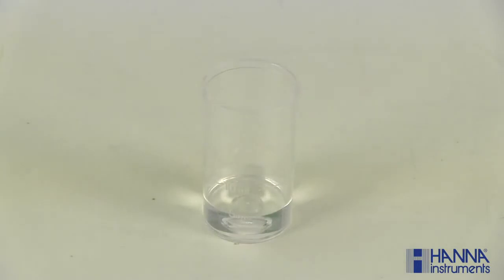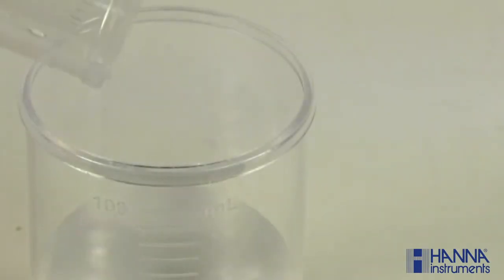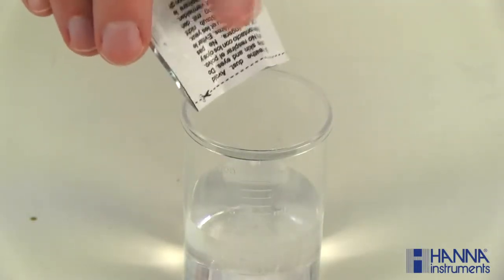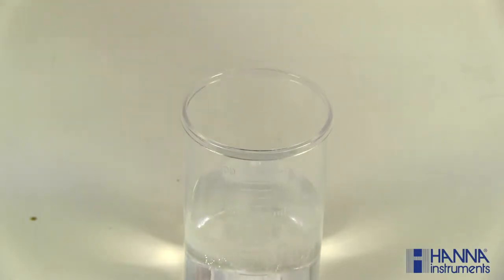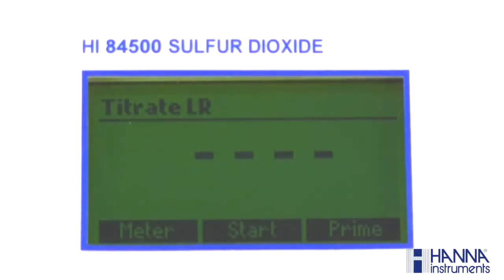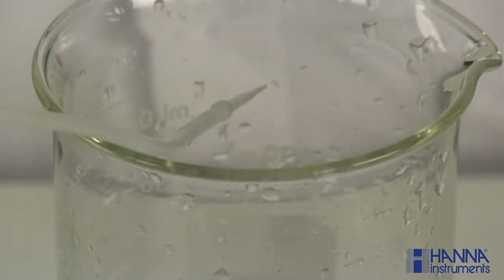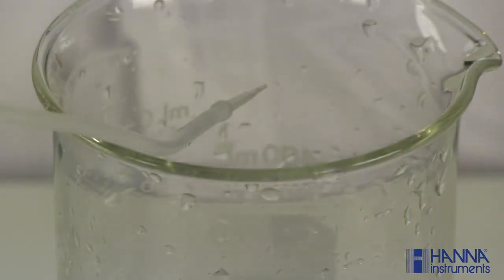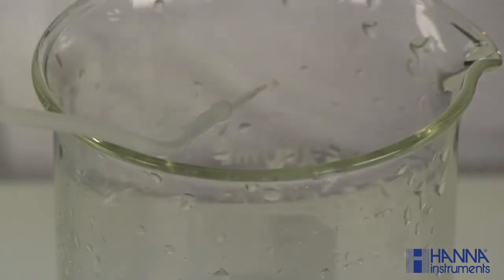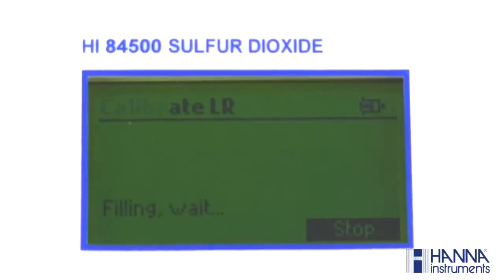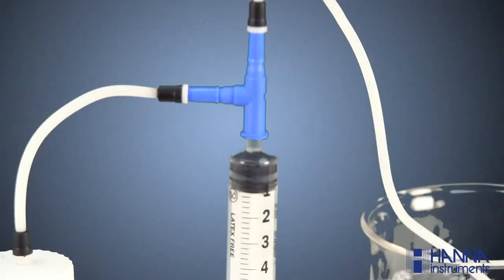Next, fill the 20 milliliter beaker up to the 5 milliliter mark with HI84500-60 acid reagent and add it to the 100 milliliter beaker. Add the contents of 1 packet of HI84500-62 stabilizer packet to the 100 milliliter beaker. Press the Cal key. Place the dosing tip over a waste beaker. This is important. A small amount of titrant is dispensed when the pump resets. Press Start and wait for the syringe to refill.